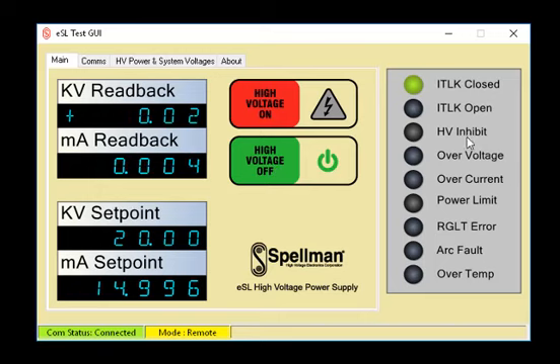Press the green high voltage off button and the generation of high voltage will stop. The fault panel will display any faults generated during operation. To clear a fault, press the green high voltage off button.